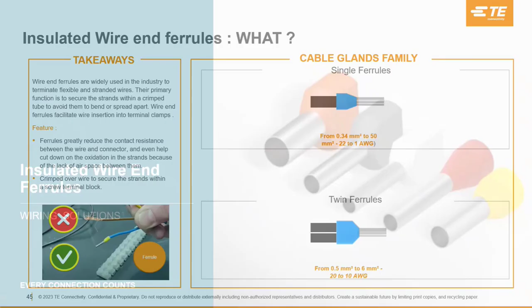Ferrules are widely used in industry to terminate flexible and stranded wire, both kinds of wire. Their primary function is to secure the strands within a crimp tube, to avoid bending or spreading apart. So the key feature of a ferrule is to reduce the contact resistance between the wire and the conductor or connector, and even help cut down oxidation.